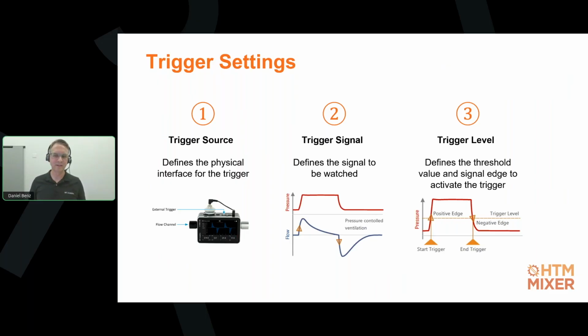In addition to the actual value of when it should trigger, we also need to define whether the trigger shall be activated when the threshold is reached on a rising edge or a falling edge of the signal. You will find such trigger settings on all gas flow analyzers. But it might very well be that you have never touched them, and more about that in just a minute.